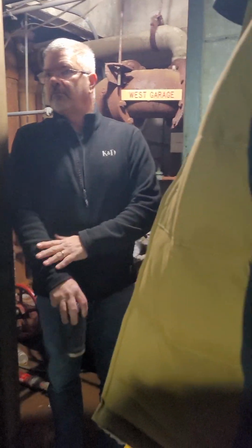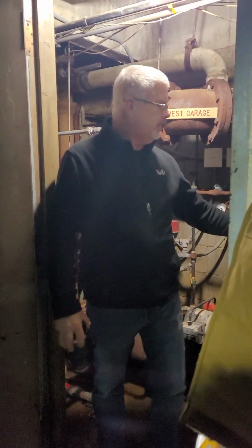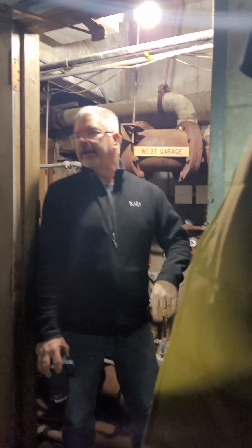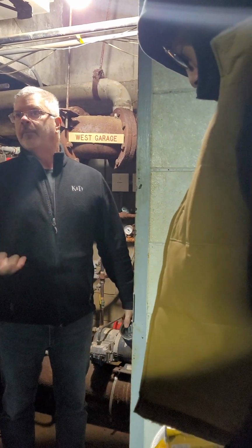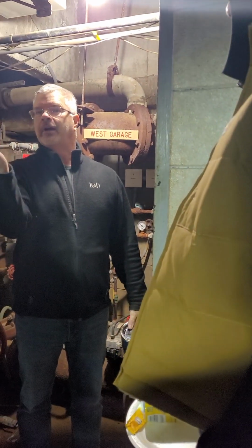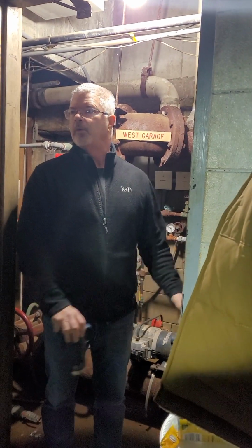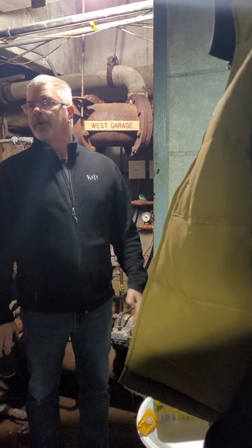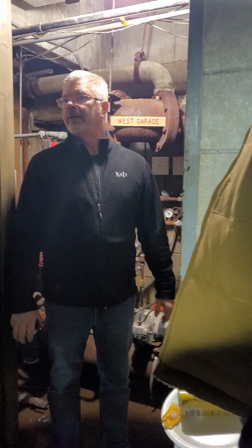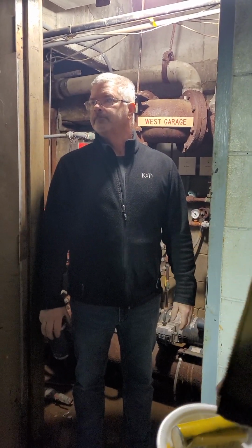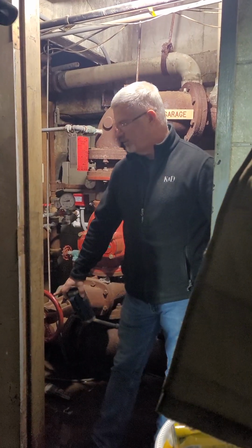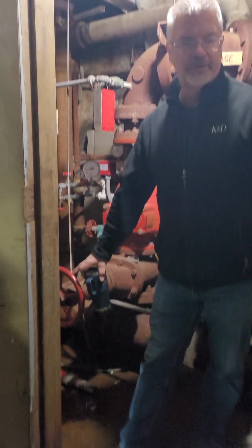Turn it one way, make sure it stops flowing, and basically if you can do that, you can leave it. Then we'll open this up and drain down everything we can. The problem when it's freezing temperatures is you probably have ice in the system somewhere, but we'll drain what we can, and then call up the sprinkler company and have them come make the repair. In an emergency, these are your two most important things to do - these two valves.